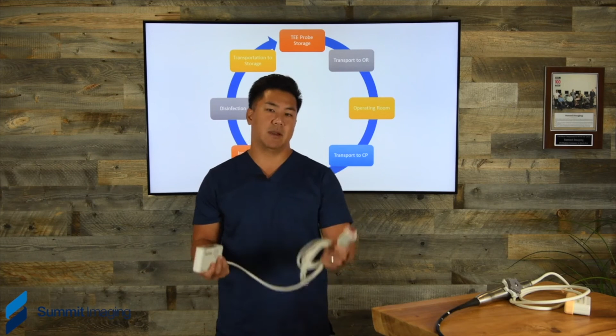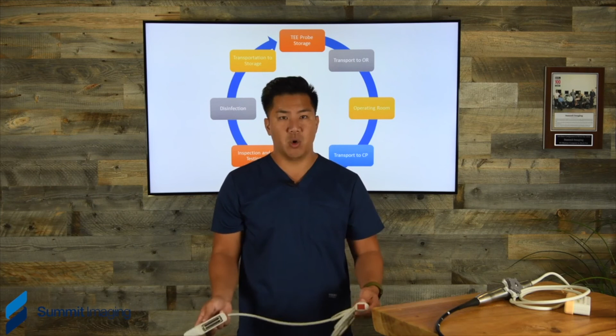So now we've got a standard probe, just a cardiac sector transducer, and we recommend the same thing: coiling it up, holding the can in one hand, holding the transducer in the other. The difference is the crystal is right on top instead of facing forward like the TEE probe, but the same issues apply: you want to protect this crystal, especially from hitting the can. And the issue, sometimes, when we see totes being used with T-probes and standard probes, is that they go into a box and then the crystal is next to the connector. As people walk down the hall, the crystal starts banging onto the connector and therefore gets damaged, because this connector is full metal and this just has a rubber lens covering a ceramic crystal that's very fragile.